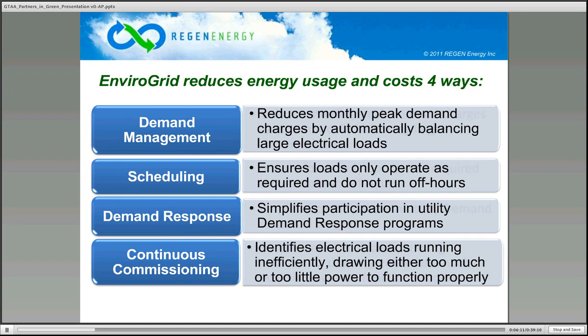Also, because we're measuring actual draw, we can see when units are starting to use more electricity than they ought to, and that indicates some kind of problem, maybe a dirty filter or something malfunctioning with a compressor. That can be attended to. If they go out of spec, an alert is generated and we can dispatch service.